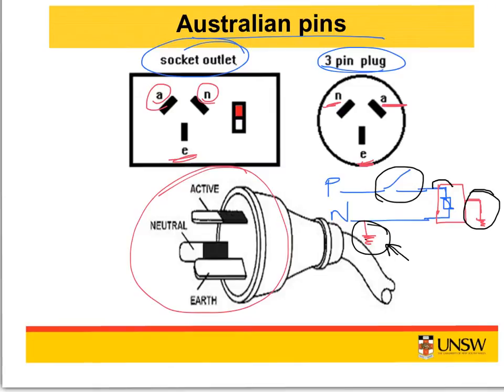Therefore, the grounding wire essentially becomes connected as a load. So the low resistance of the grounding wire causes it to draw a very large amount of current when it becomes inadvertently connected as a load, which in turn causes the circuit breaker feeding the active wire to trip. So you see here the current, let's say the circuit breaker is closed. So when the phase wire gets accidentally connected to the ECP, the current flows through this ECP here, and then because it's also grounded, the current flows to the neutral wire this way. So the path is closed. So the grounding wire now essentially becomes the load in this circuit.